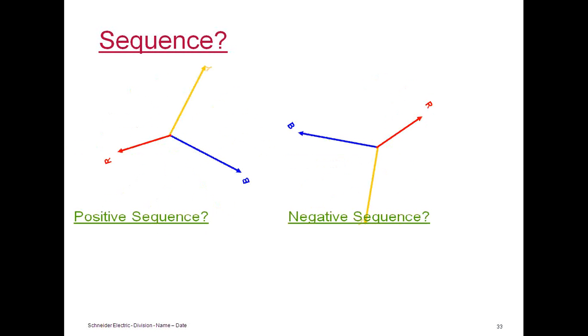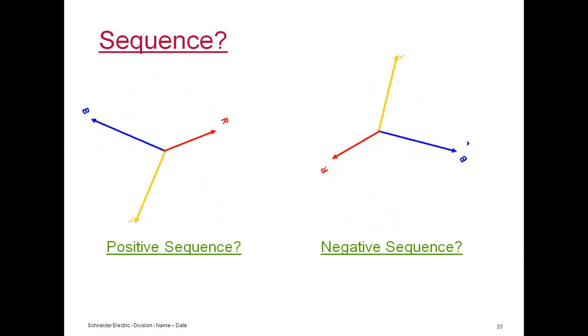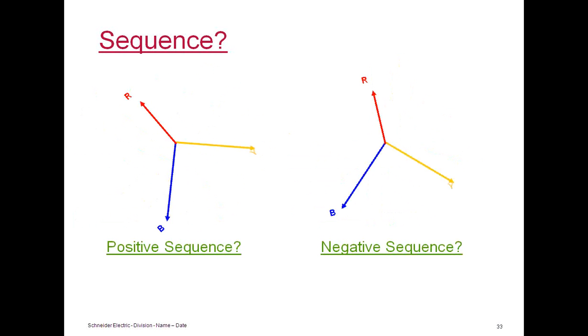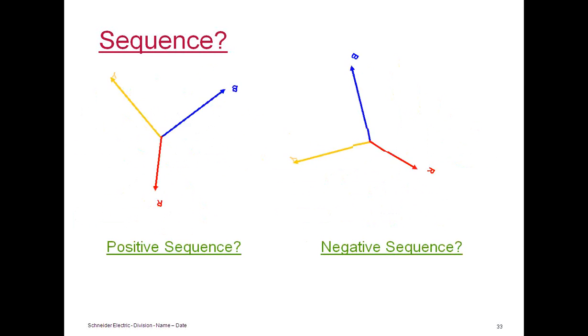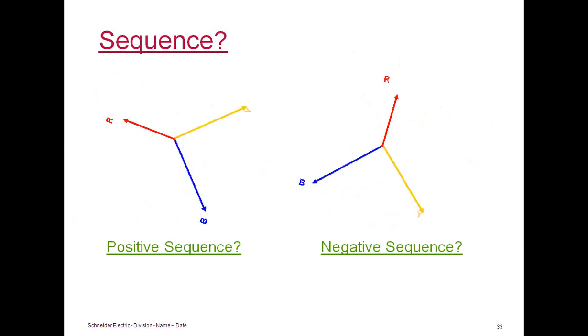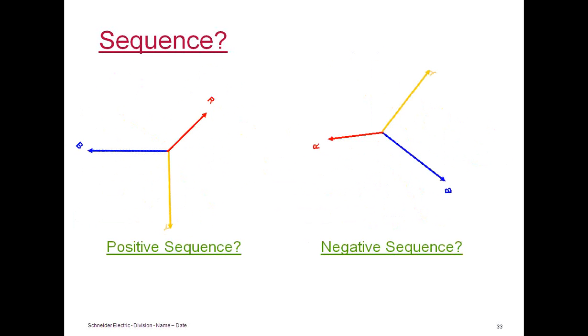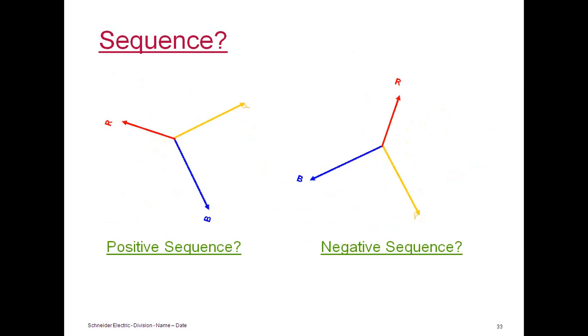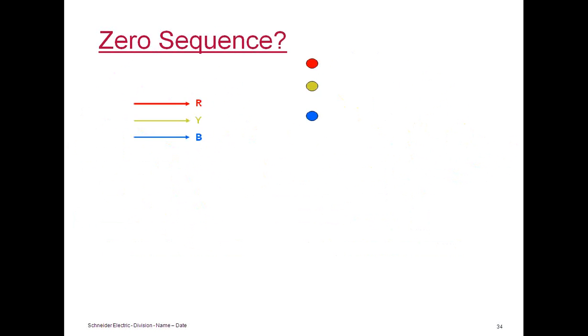sequences in harmonics. One is the anti-clockwise rotation, called positive sequence or plus sequence. We have clockwise rotation of vectors in three phase in harmonics, called negative sequence or minus sequence harmonics. And we have one more sequence called zero sequence, where we have harmonics in three lines but without any phase angle difference. So we have positive sequence, negative sequence, and zero sequence in harmonics.